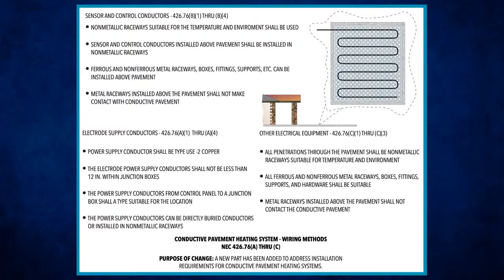Now, one we did cover is 76 here, and he'll get in and talk about the electrode supply conductors. But the main thing behind this, and your sensor and control conductors or any other electrical equipment, is there cannot be any type of metal raceways that make contact with a conductive pavement. I agree 100% with that. We just PVC'd it. That's what it tells you to do: use non-conductive or non-metallic raceway. I don't see why you wouldn't use PVC anyway. It's cheapest, easiest. Sure, but that's why we did a few different ones here, because there were a lot of things people hadn't seen, to give them an idea of exactly what they're looking at and what they're required to do.